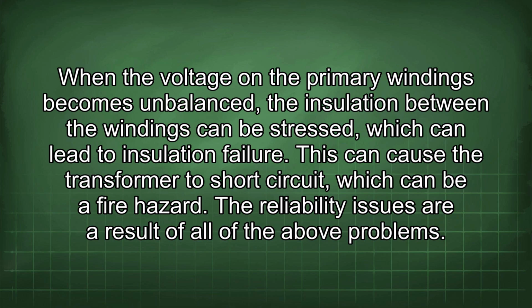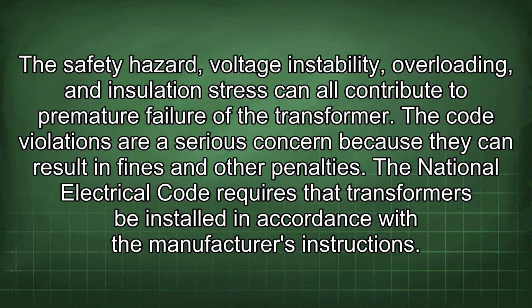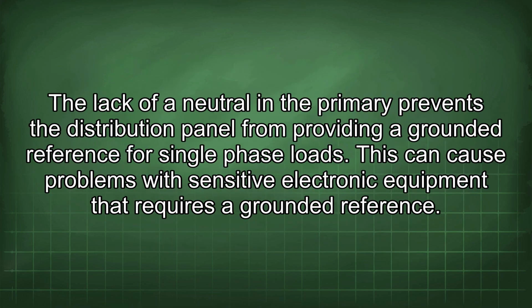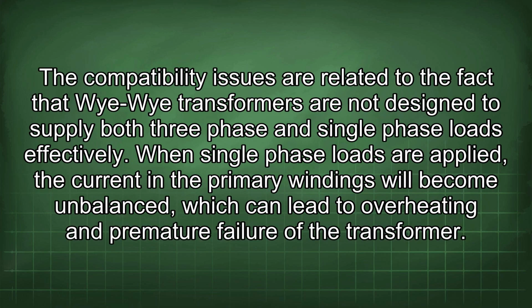The reliability issues are a result of all of the above problems. The safety hazard, voltage instability, overloading, and insulation stress can all contribute to premature failure of the transformer. The code violations are a serious concern because they can result in fines and other penalties. The National Electrical Code requires that transformers be installed in accordance with the manufacturer's instructions. The lack of a neutral in the primary prevents the distribution panel from providing a grounded reference for single-phase loads. This can cause problems with sensitive electronic equipment that requires a grounded reference. The compatibility issues are related to the fact that Wye-Wye transformers are not designed to supply both three-phase and single-phase loads effectively. When single-phase loads are applied, the current in the primary windings will become unbalanced, which can lead to overheating and premature failure of the transformer.